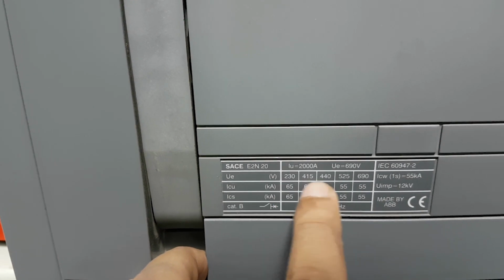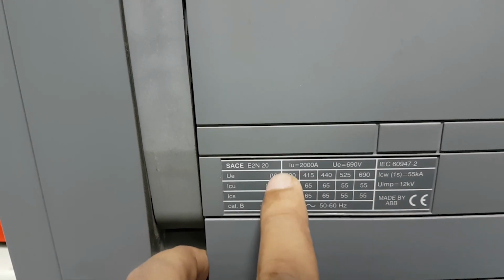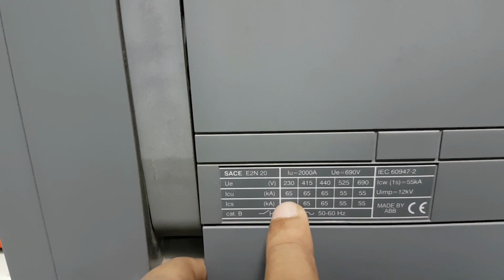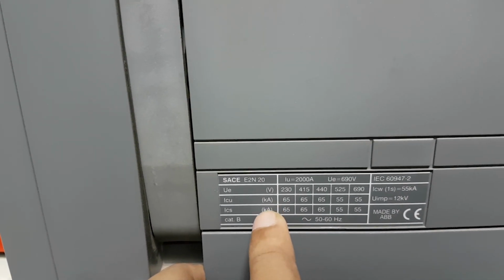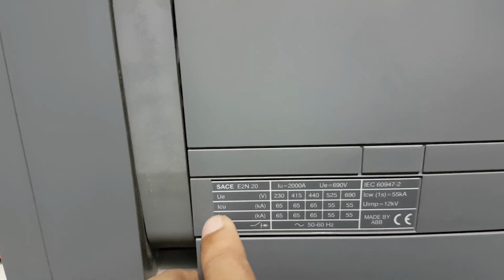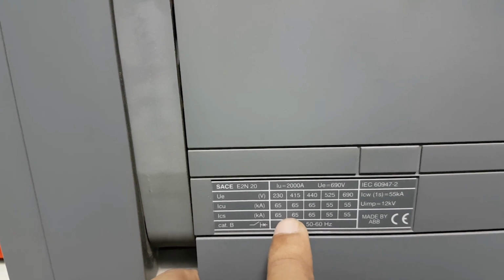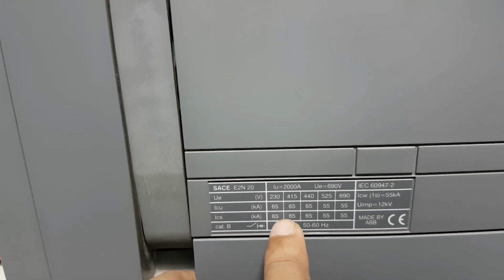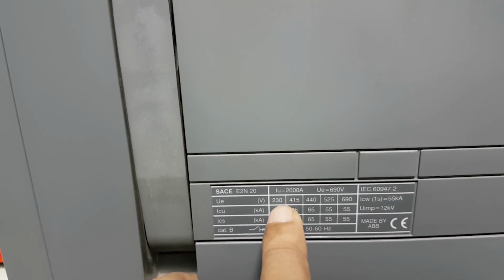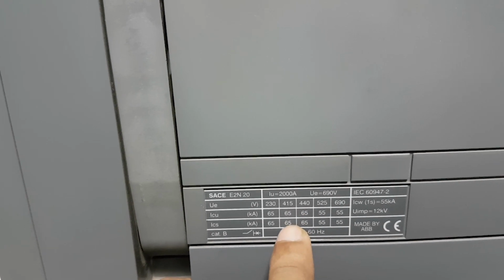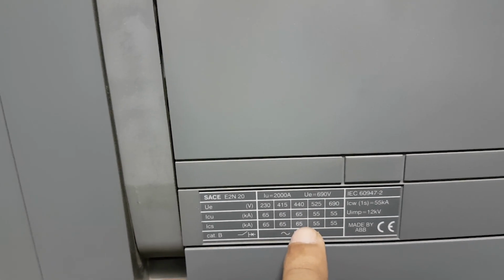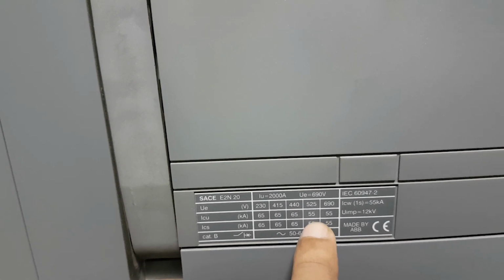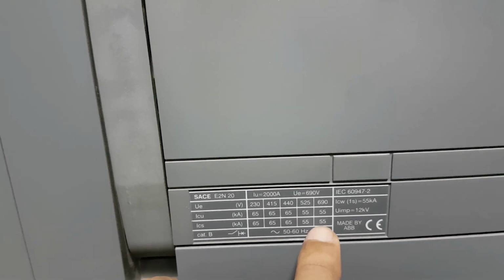This is a chart showing, for each voltage, what the kA rating of short circuit current is. 65 kA at 230 volt. At 415 volt it's also 65. 440 volt is 65, and 525 and 690 volt is 55.